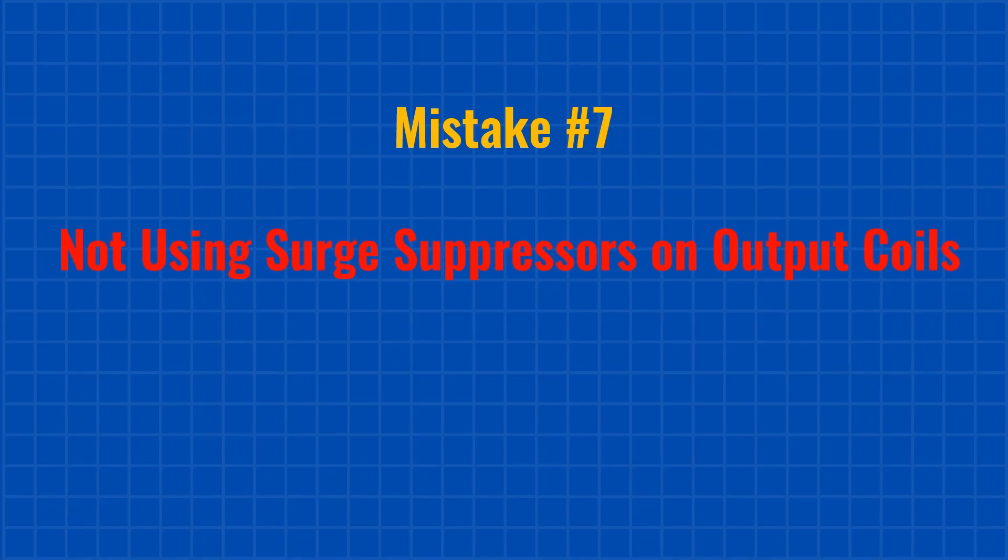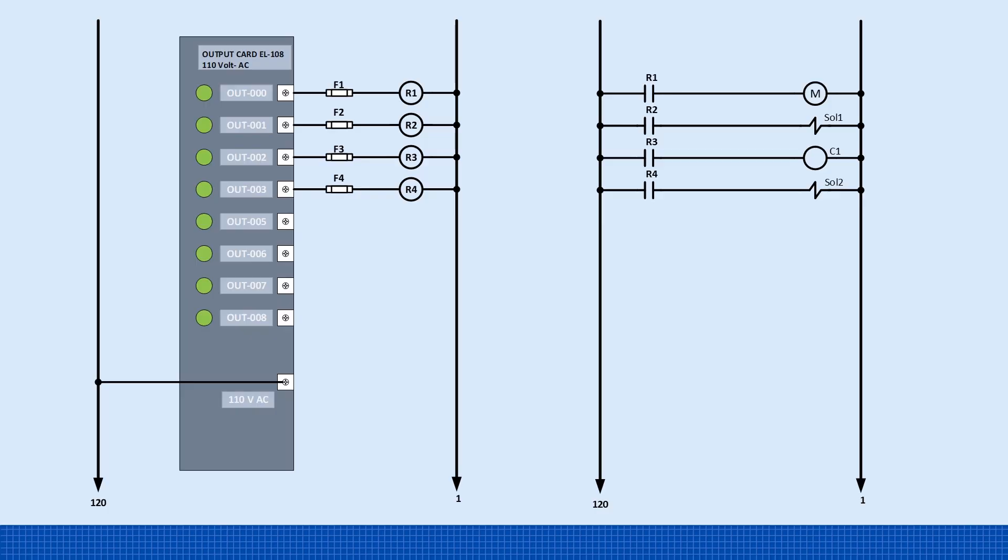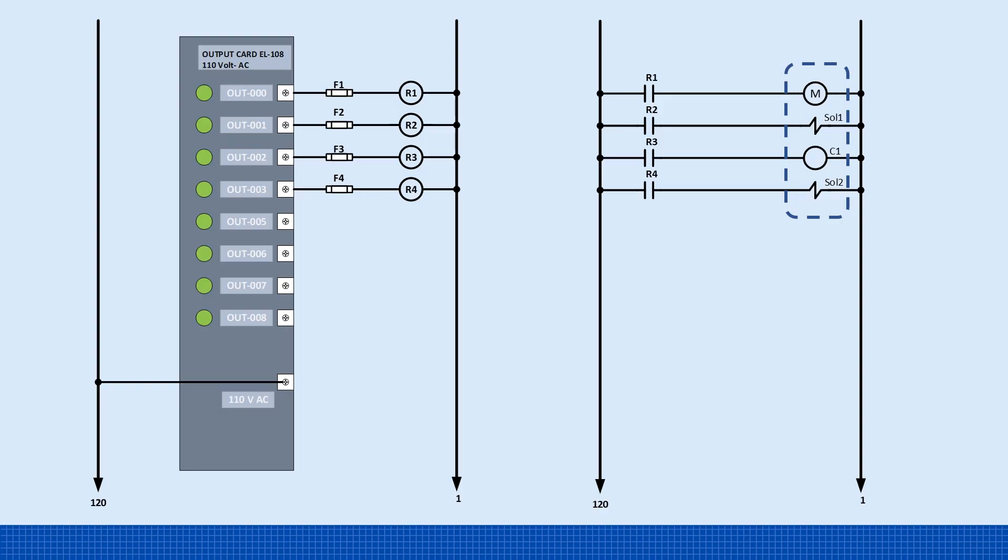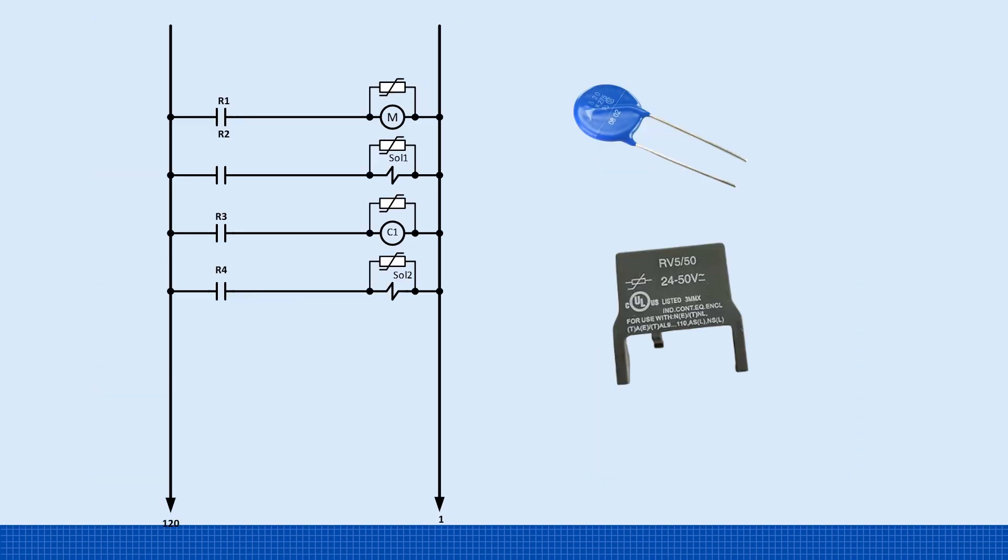Mistake number 7. Not using surge suppressors on output coils. Even after isolating the PLC outputs using relays to drive contactors, motor starters, or solenoids, voltage spikes can still occur, especially when switching inductive loads. These spikes may not return through the PLC output, but they can propagate through the control panel's power and ground lines, potentially disrupting or damaging the PLC CPU, input cards, and other sensitive electronics. There are two effective ways to protect your control system from voltage spikes caused by inductive loads.